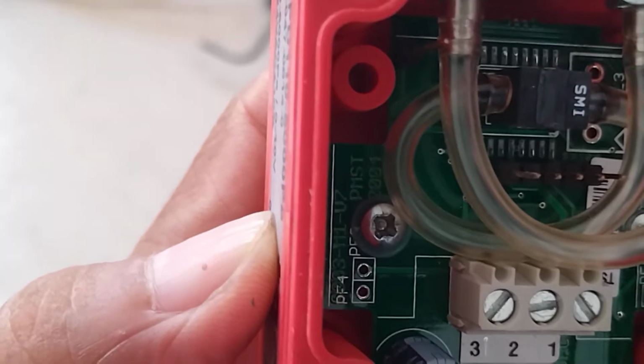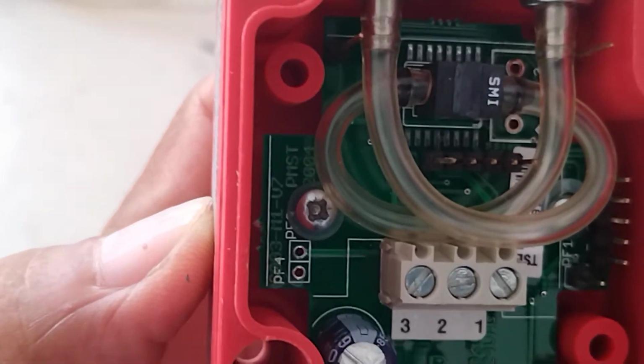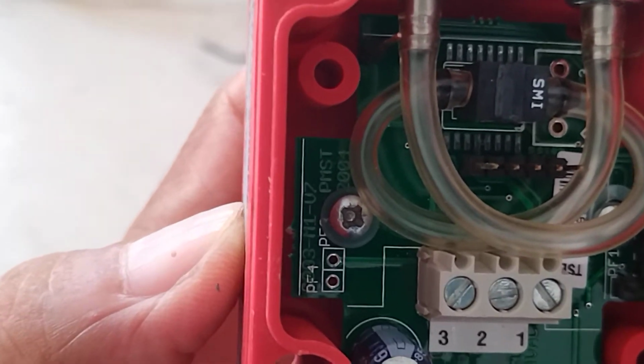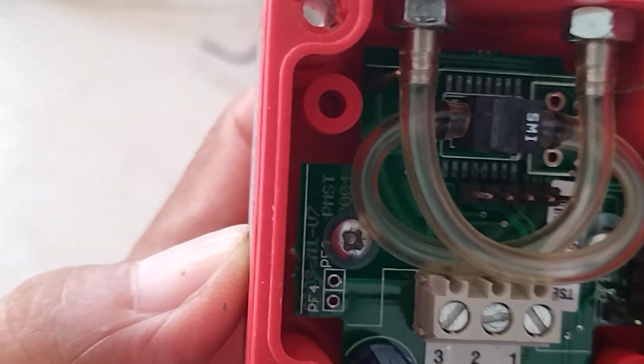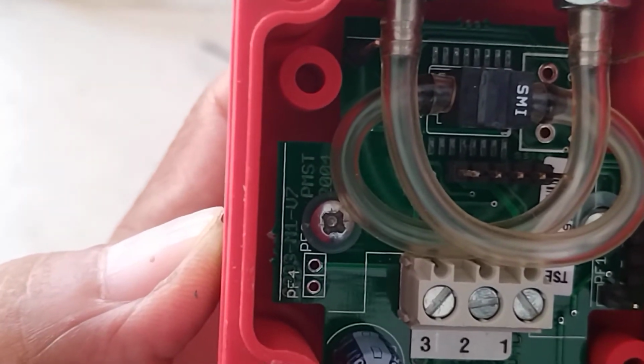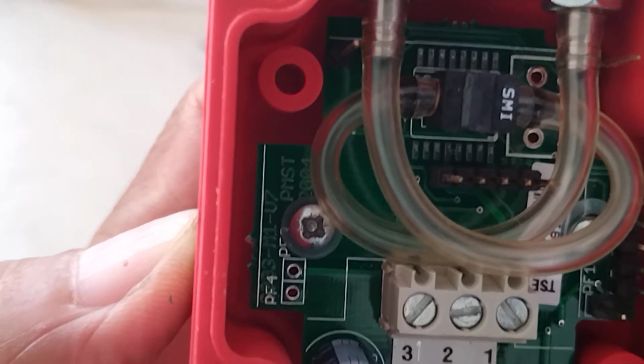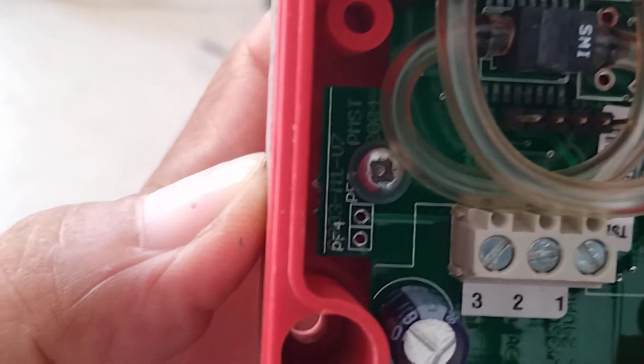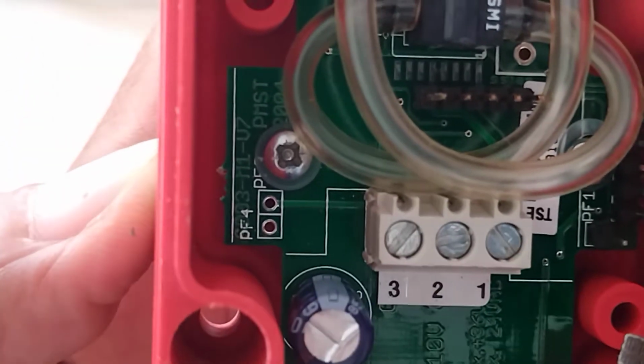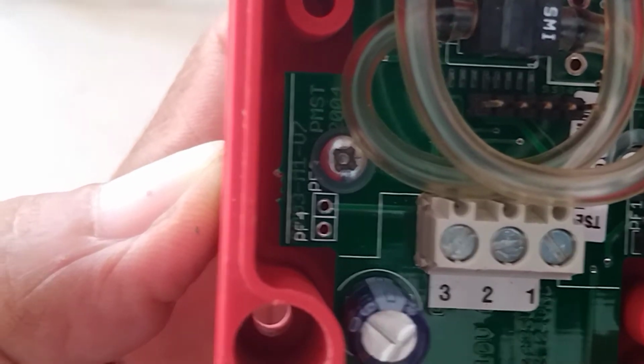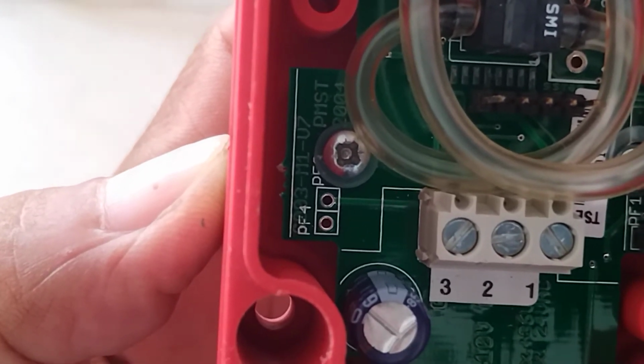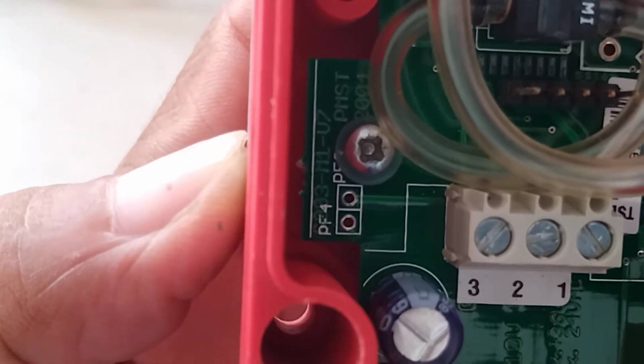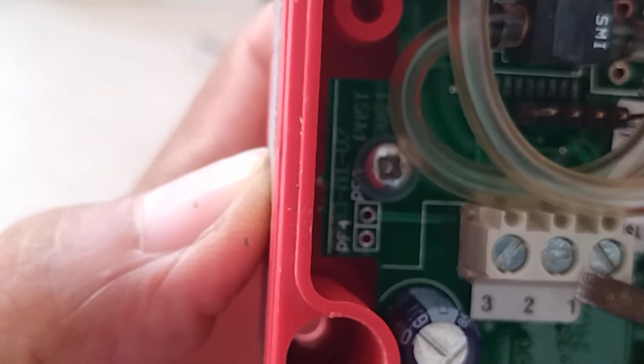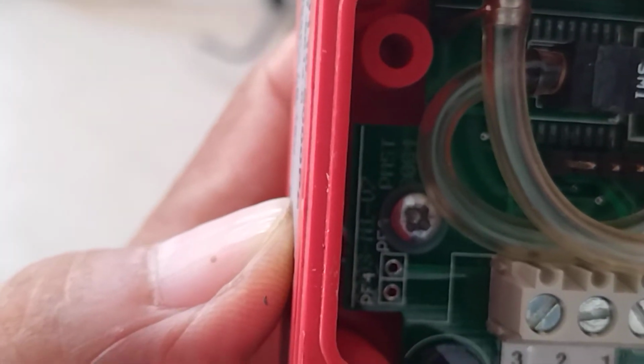The differential pressure transmitter will transmit the differential pressure, or give you the differential pressure reading across, let's say, a fan. This device will give you a control signal output. In terminal 2, it will give you a 0 to 10 volt signal based on the differential pressure being sensed by this device.